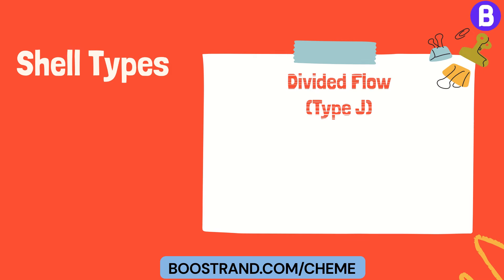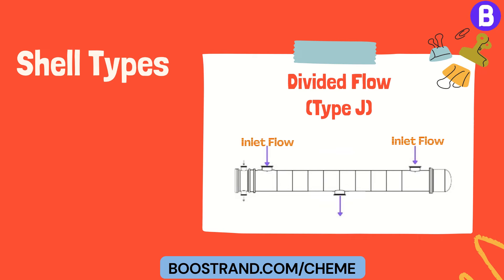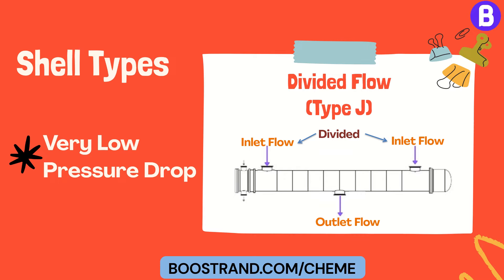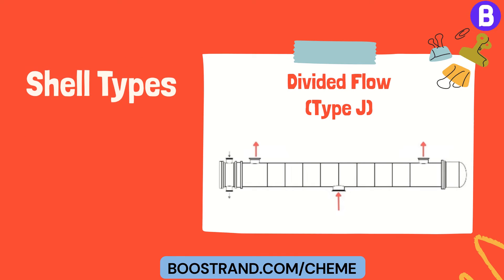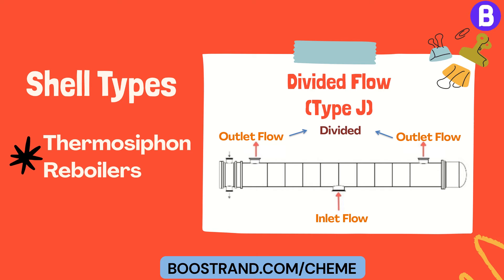Divided flow, Type J: this is another shell type where either the inlet flow is divided while the outlet flow exits in one nozzle, used in condensation applications that require a very low pressure drop — in this case the shell type is J21. On the other hand, if the outlet flow is divided, which is commonly the case for thermosyphon reboilers, the shell type is J12.